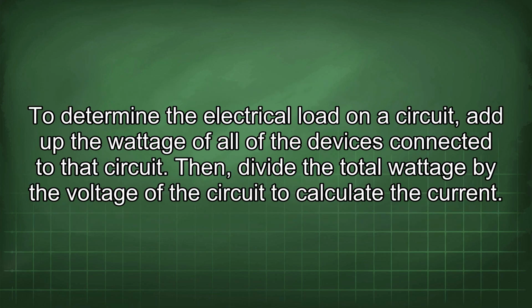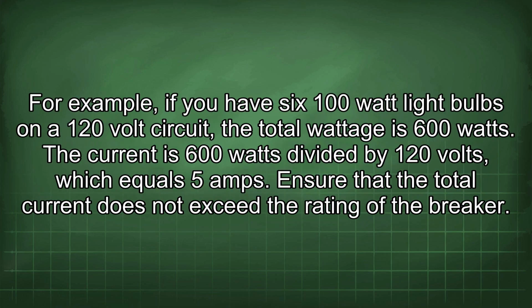To determine the electrical load on a circuit, add up the wattage of all of the devices connected to that circuit. Then, divide the total wattage by the voltage of the circuit to calculate current. For example, if you have 6 100-watt light bulbs on a 120-volt circuit, the total wattage is 600 watts. The current is 600 watts divided by 120 volts, which equals 5 amps. Ensure that the total current does not exceed the rating of the breaker.